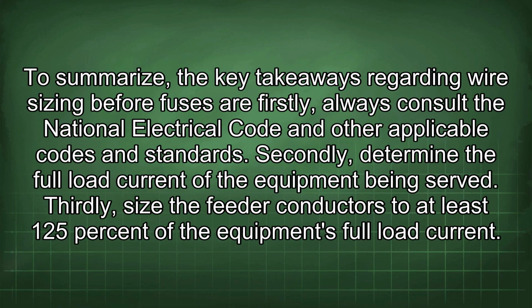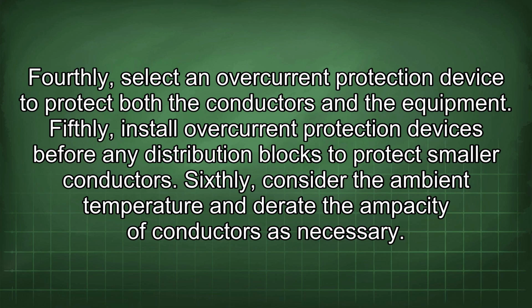To summarize, the key takeaways regarding wire sizing before fuses are: firstly, always consult the National Electrical Code and other applicable codes and standards. Secondly, determine the full load current of the equipment being served. Thirdly, size the feeder conductors to at least 125% of the equipment's full load current. Fourthly, select an overcurrent protection device to protect both the conductors and the equipment. Fifthly, install overcurrent protection devices before any distribution blocks to protect smaller conductors. Sixthly, consider the ambient temperature and derate the ampacity of conductors as necessary.